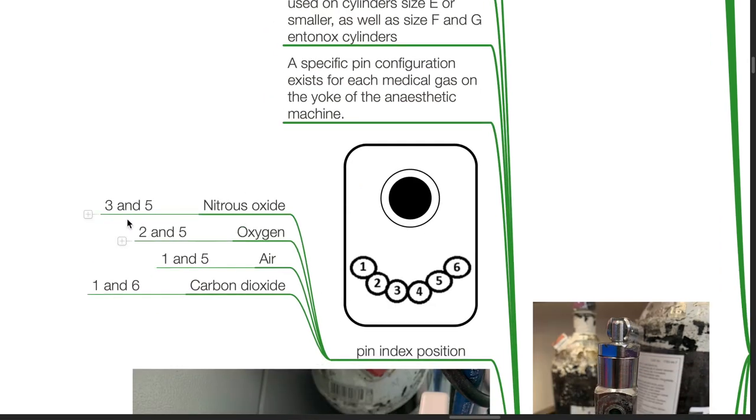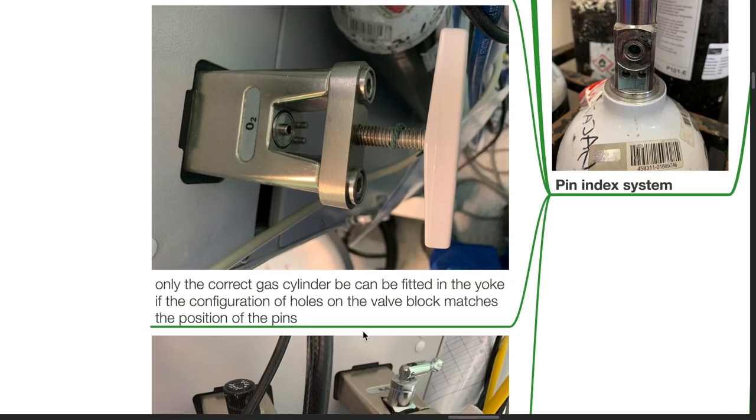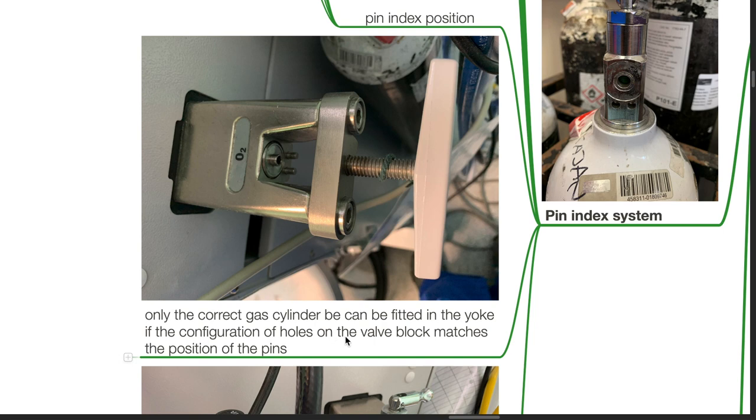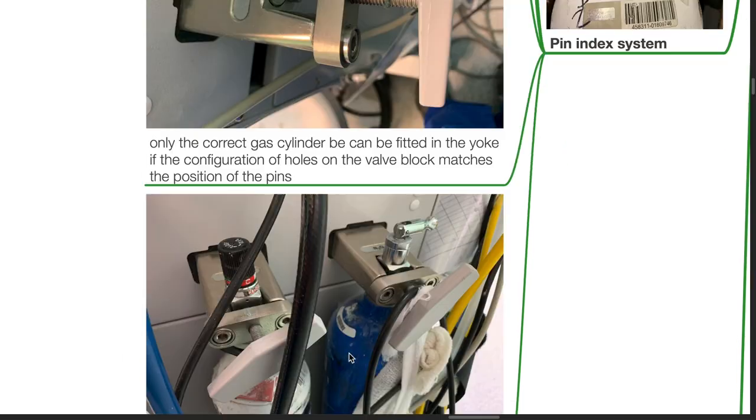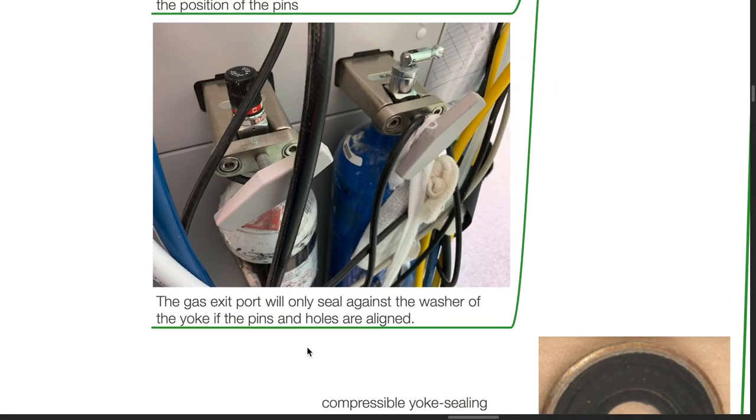Nitrous oxide 3 and 5, oxygen 2 and 5, air 1 and 5, and carbon dioxide at 1 and 6 pin index positions. Only the correct gas cylinder can be fitted in the yoke if the configuration of the holes on the valve block matches the positions of the pins. The gas exit port will only seal against the washer of the yoke if the pins and holes are aligned.